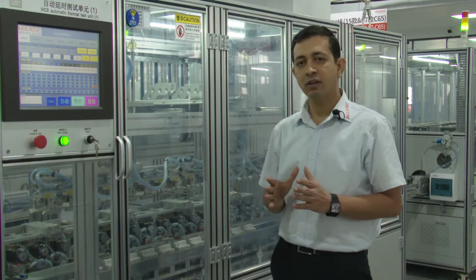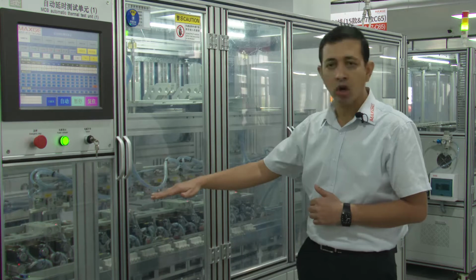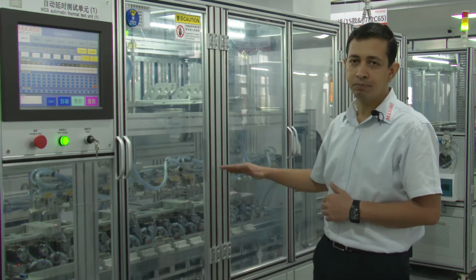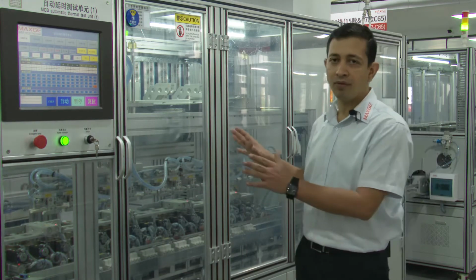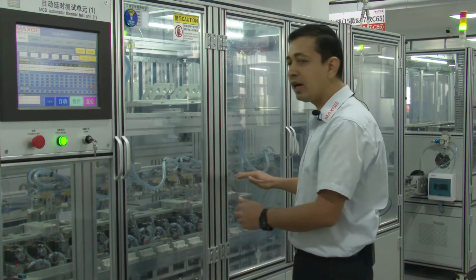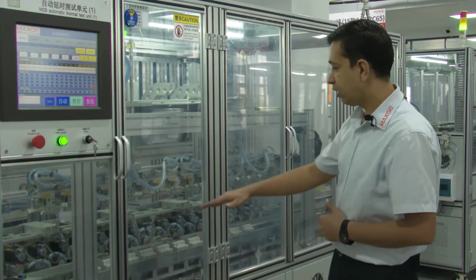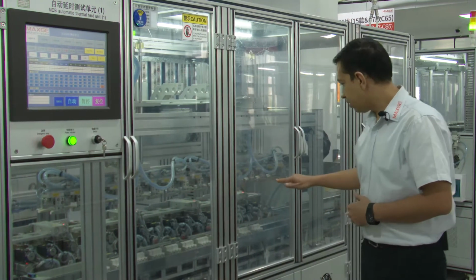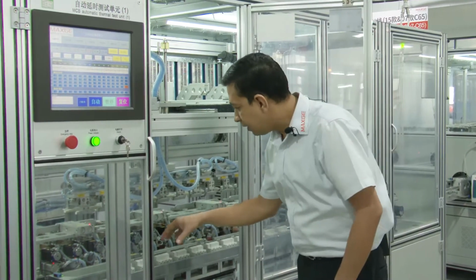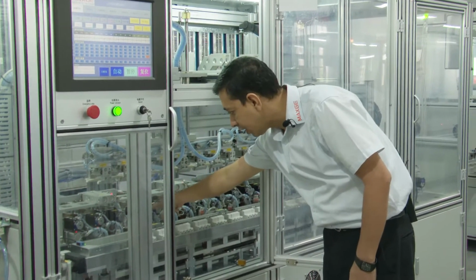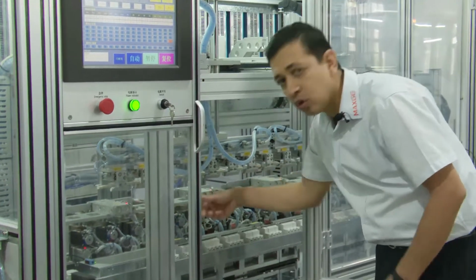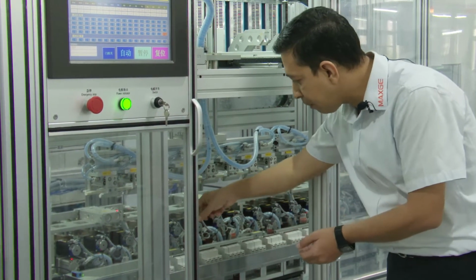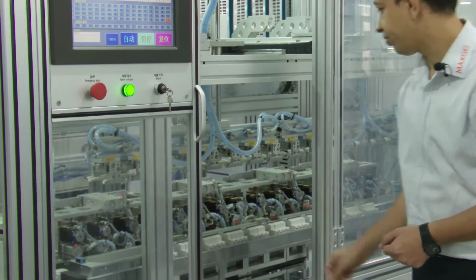This test is qualified once we have good quality of calibration maintained. That's why we have done all the process through the automatic calibration machine. Here you can see these are the motors which are doing the automatic calibration, and these are the electrodes where the currents are getting passed during the calibration process.